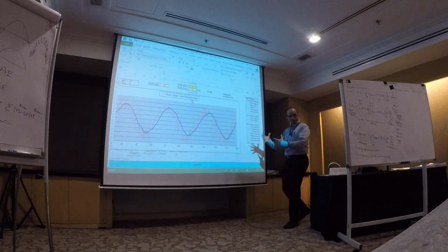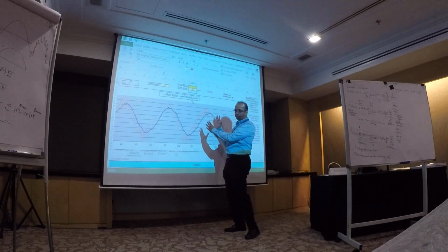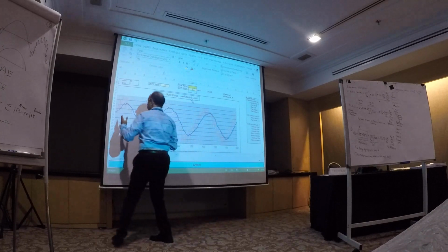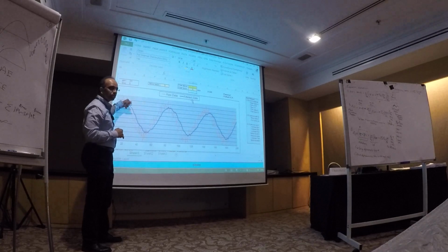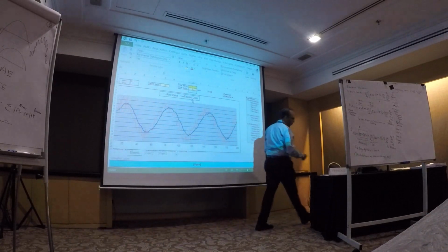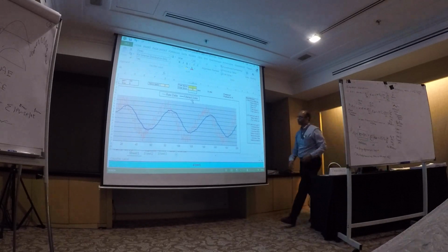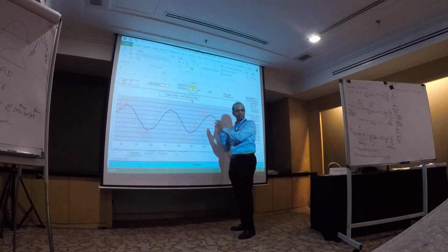You notice something? The blue line is starting to look really nice. So what's happening to the blue line? It's starting to shift, right? So what's happening is the process is reaching a peak here, but the filtered output is reaching a peak later. In fact, if I put in more filter, it starts to shift further and further. You are starting to introduce a lag in the process.